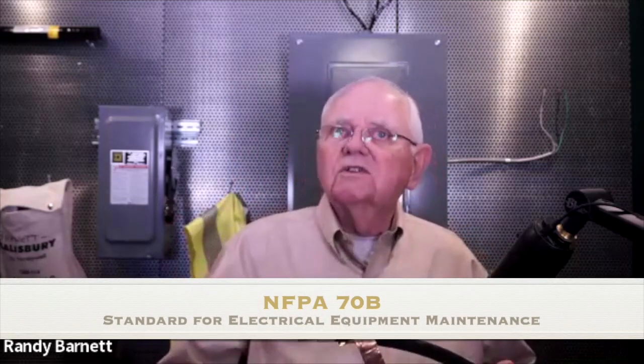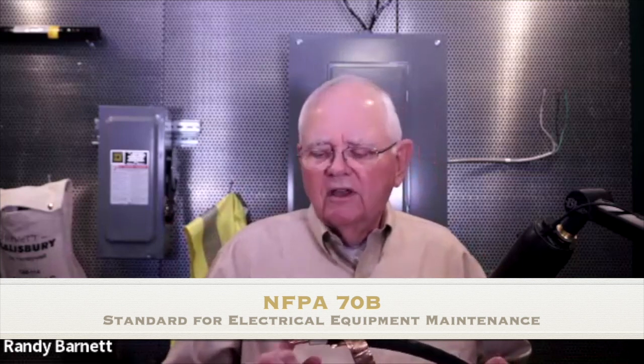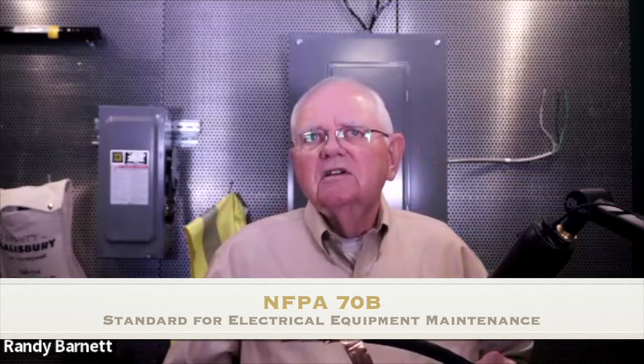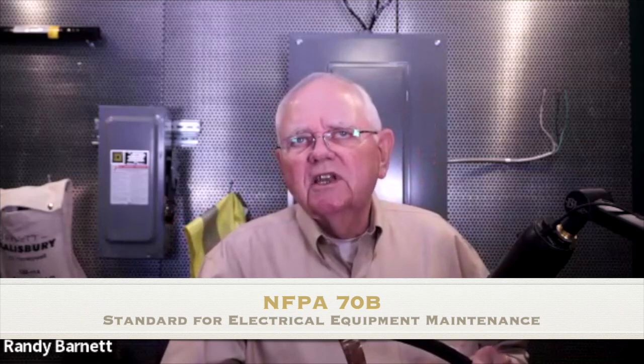So there are two types of tests that we often perform to check this insulation. You want to go to your NFPA 70B, the standard now for electrical equipment maintenance, and check that out. But when it comes to this medium voltage dielectric insulation, we might want to do a DC high pot test, where we might apply up to 35,000 volts to this particular insulation and see if any current leaks through.